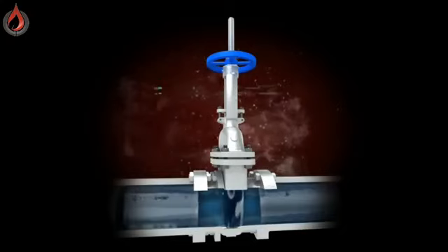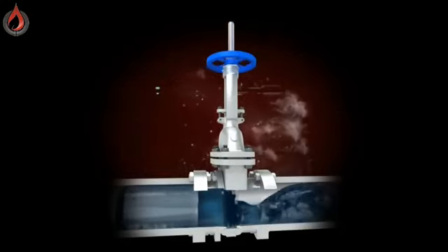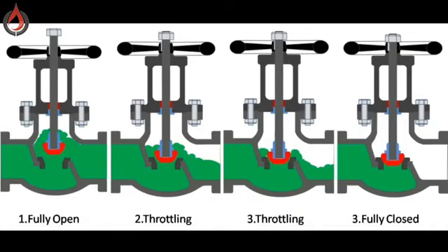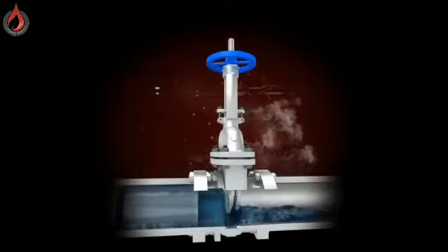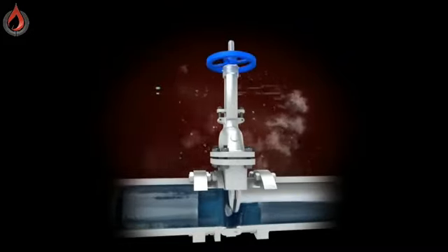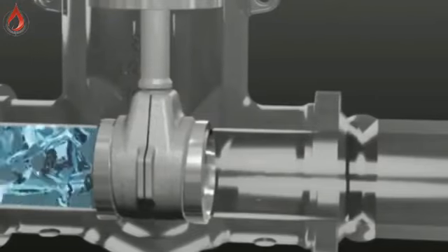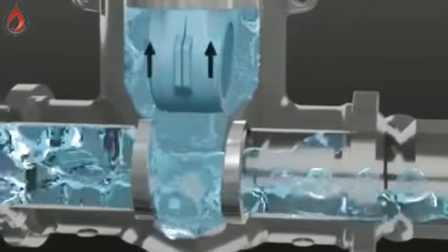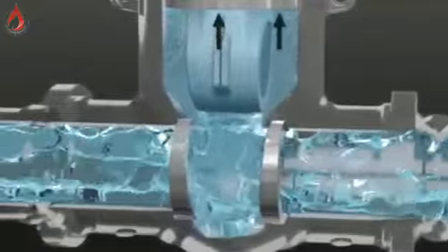Gate valves are not usually used to regulate flow because the valving element can be damaged when in the partially open position. These valves are pretty much kept either fully open or fully closed. Gate valves can be used in high temperature and high pressure environments.